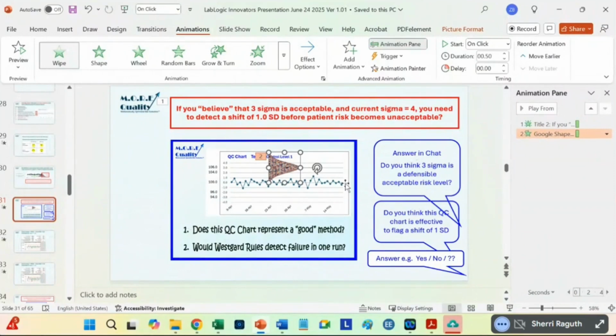I sat down with my medical director and said, for this analyte at this level, how far can the value shift before the doctor's going to react differently? So say you've got a sodium and your QC sample is running at 140, or 138. Ask yourself, if I report 137, is the doctor going to do anything differently? How about 136, 135, 134? Usually about 134, people start to squirm. And you say, yeah, the doctor's going to react differently.